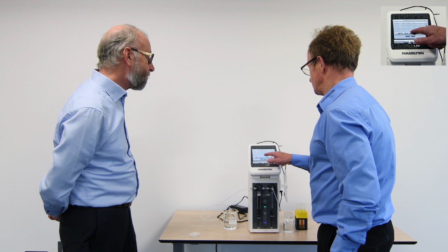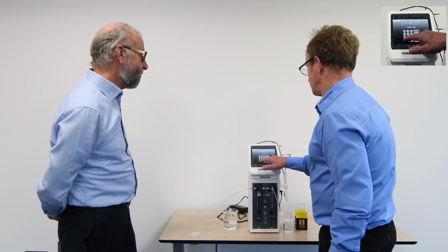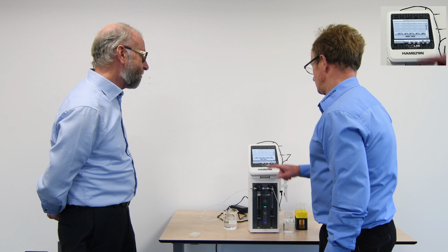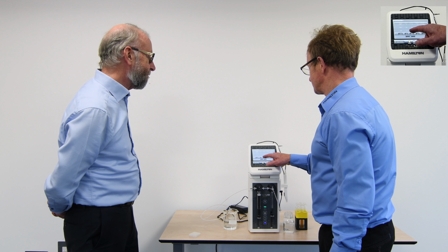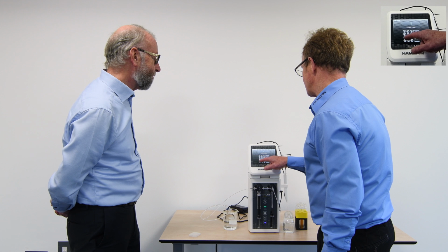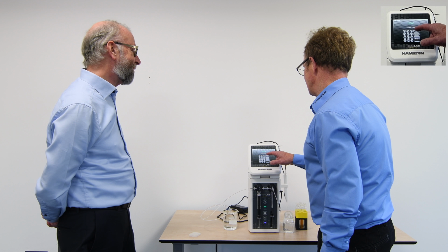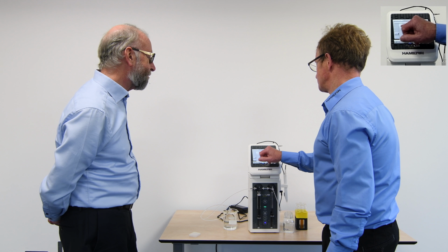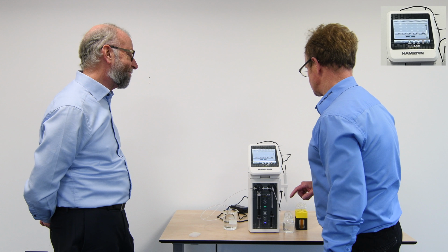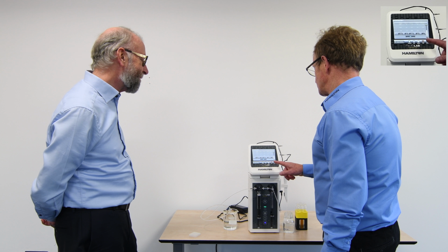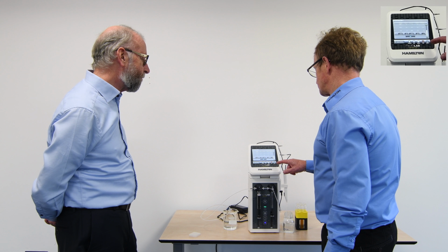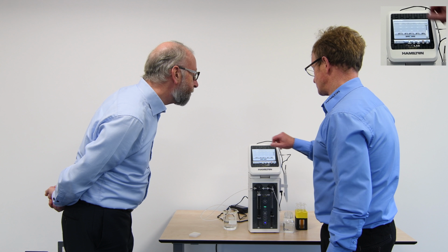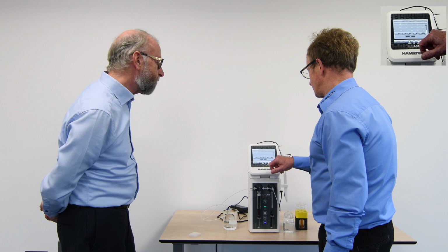So I can change this, and we put in our 5,000 microlitres, and remembering that was in negative form. So I pick one, and you can see it'll change this to put in my 10,000 microlitres in the negative form. And now if I go to validate, it says the method is valid. In other words, the steps add up. Very good. Once that's actually in, we have the information stored. We have the ability to save and loop methods, so it's actually repeating those functions.